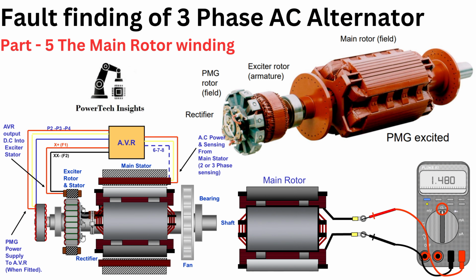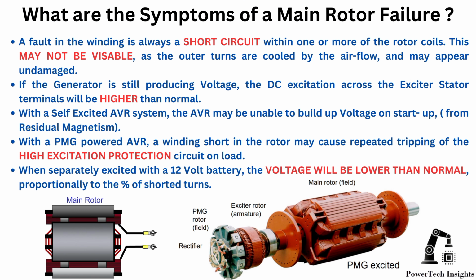Part 5. The main rotor winding. In this part, we will provide a comprehensive guide on fault diagnosis for the main rotor winding. Let's get started. Possible symptoms of the main rotor winding. A fault in the winding is always a short circuit within one or more of the rotor coils. This may not be visible, as the outer turns are cooled by the airflow and may appear undamaged.